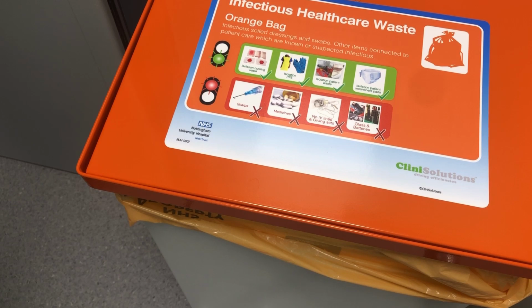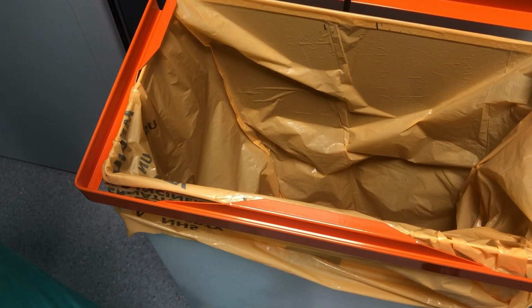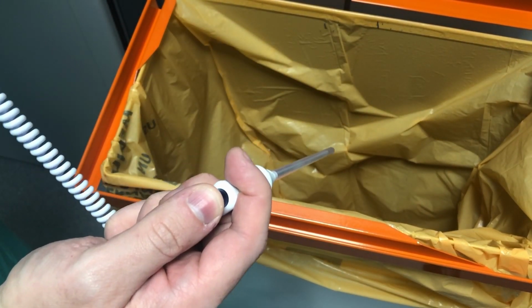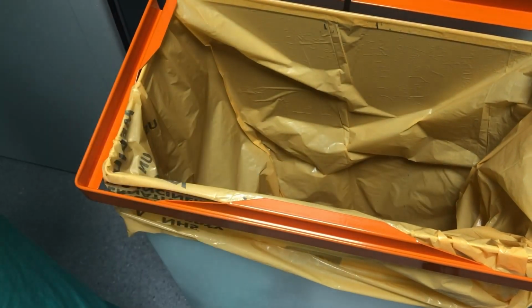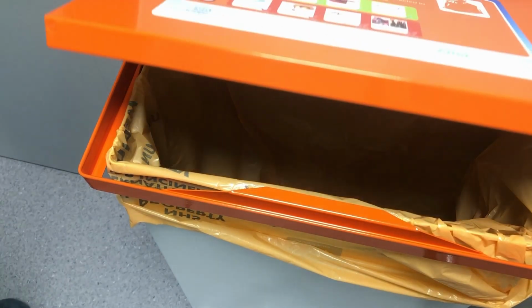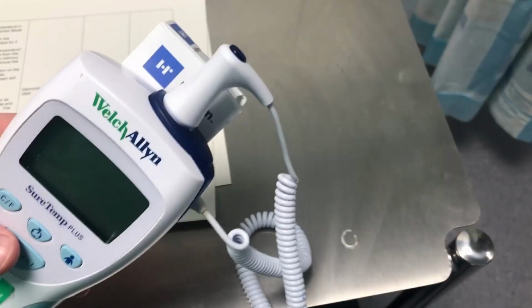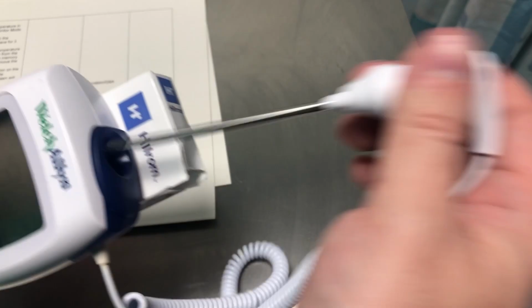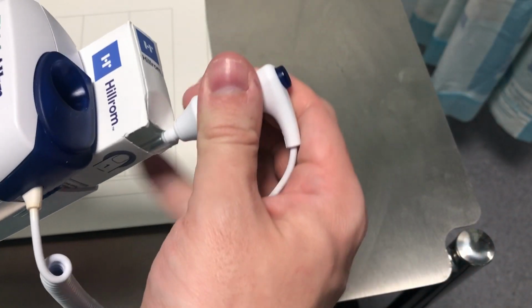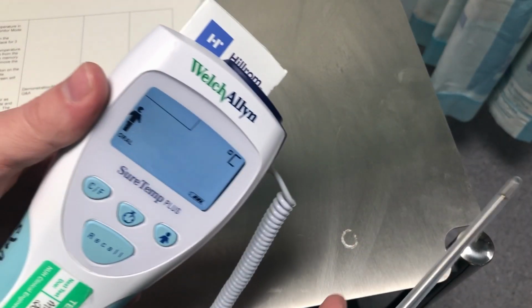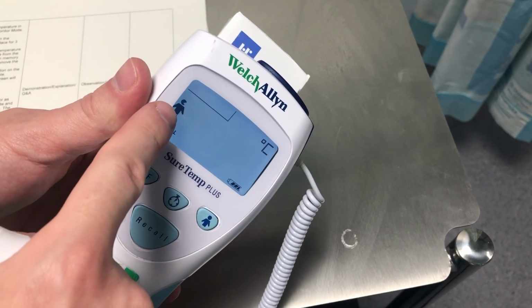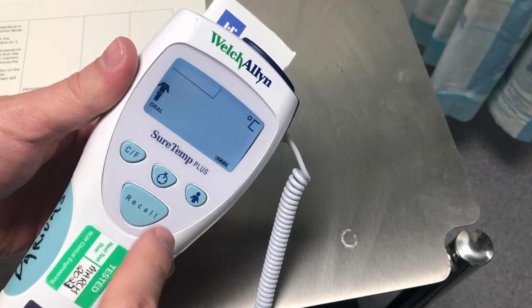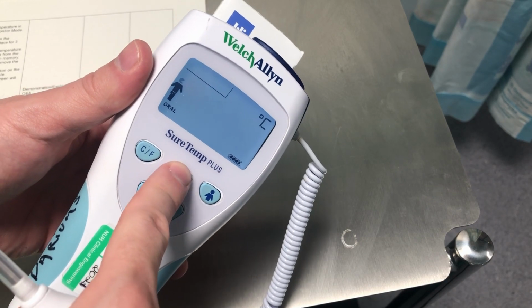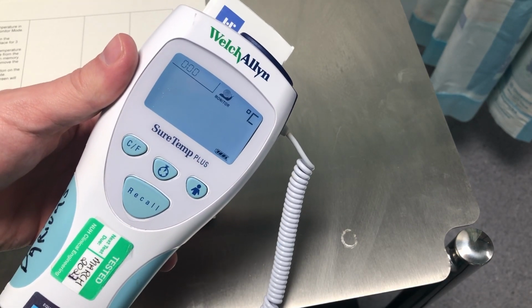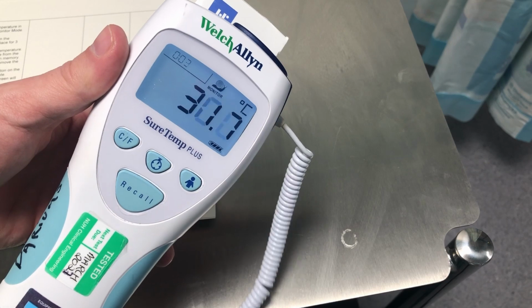And then to dispose of your used probe covers, find a bin and press the blue button that has popped up, and it should pop right off, and then return to the probe well. Monitor mode continuously displays the temperature of the probe for as long as the probe remains in place at the measurement site and remains within the operating temperature range. The patient's oral temperature will reach a final equilibrium in about 3 minutes, and 5 minutes for axilla.